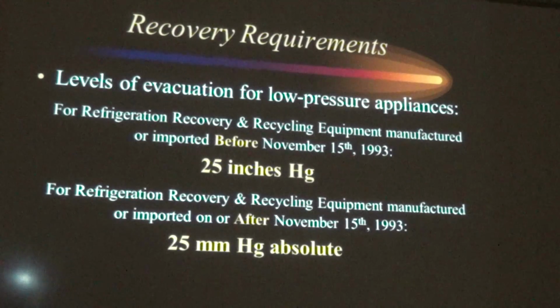Now, the chart I mentioned, the 4 inches, 10 inches, 15 inches, those were all for R22 and other high pressure refrigerants. The other half of that chart, the bottom half, is actually this. It's the low pressure. Your book, Unit 9, showed both the high and the low. But here it is. Levels of evacuation for low pressure appliances. For refrigerant recovery or recycling equipment before 1993, the number is 25 inches mercury. If it was made after 1993, it's 25 millimeters mercury. Keep that in mind. We've got 25 mm and 25 Hg for the before and after.